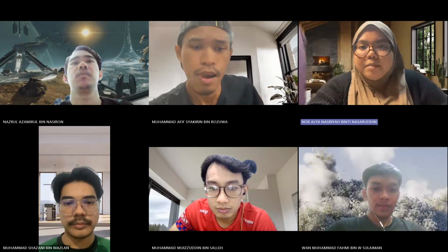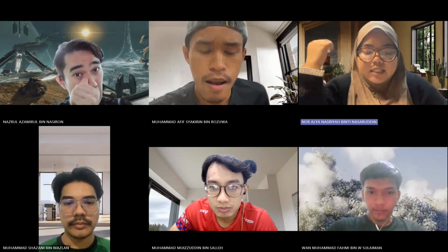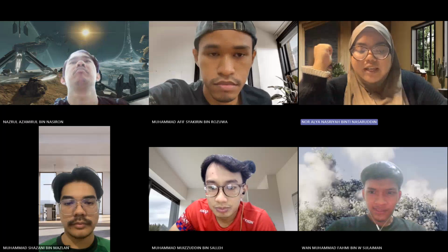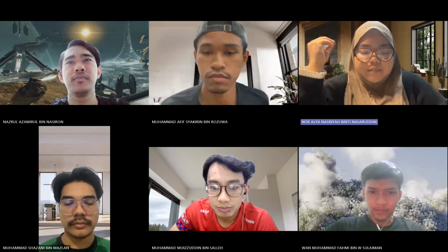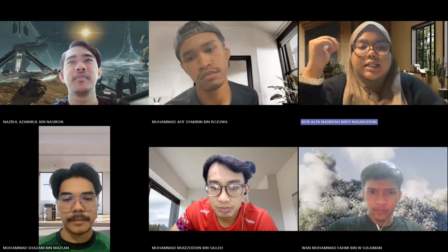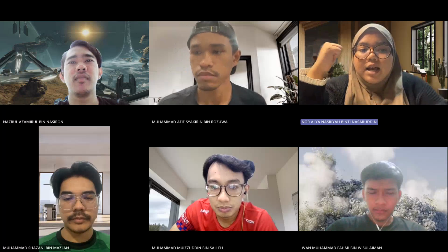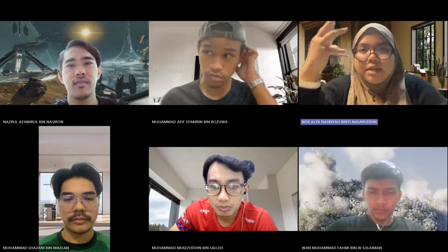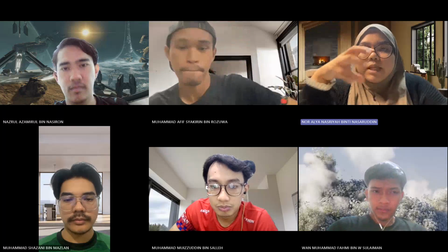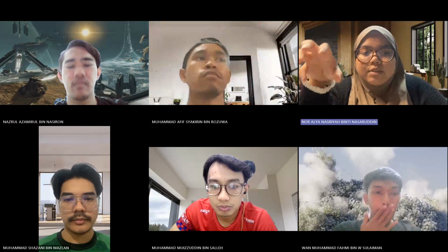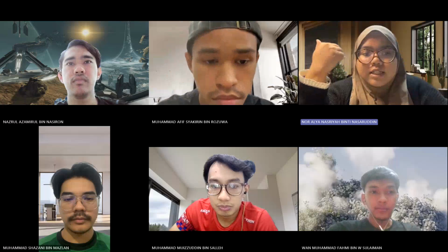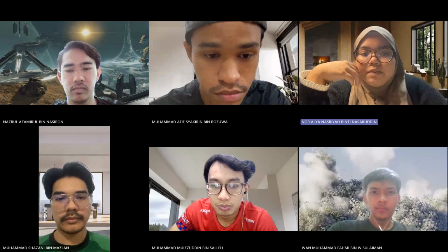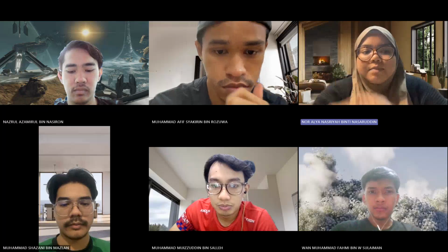All right. For my section, I researched diagnostic methods used for underground cable insulation. These include partial discharge testing, tan delta testing, thermal imaging, and online monitoring systems. These methods help engineers to identify insulation defects and to monitor cable conditions before failures occur.